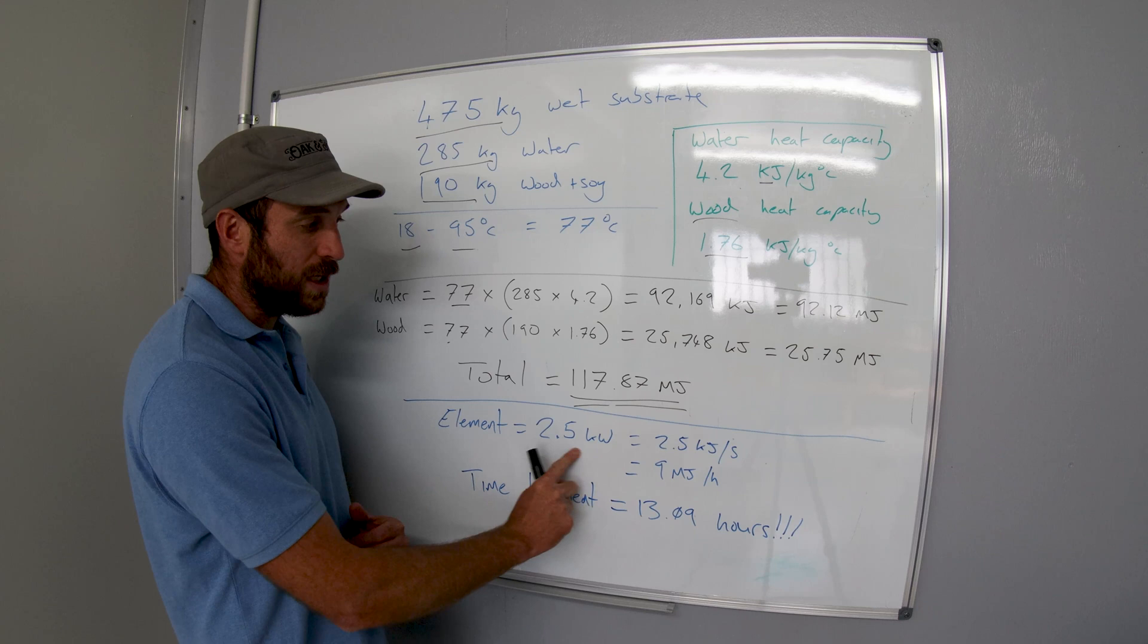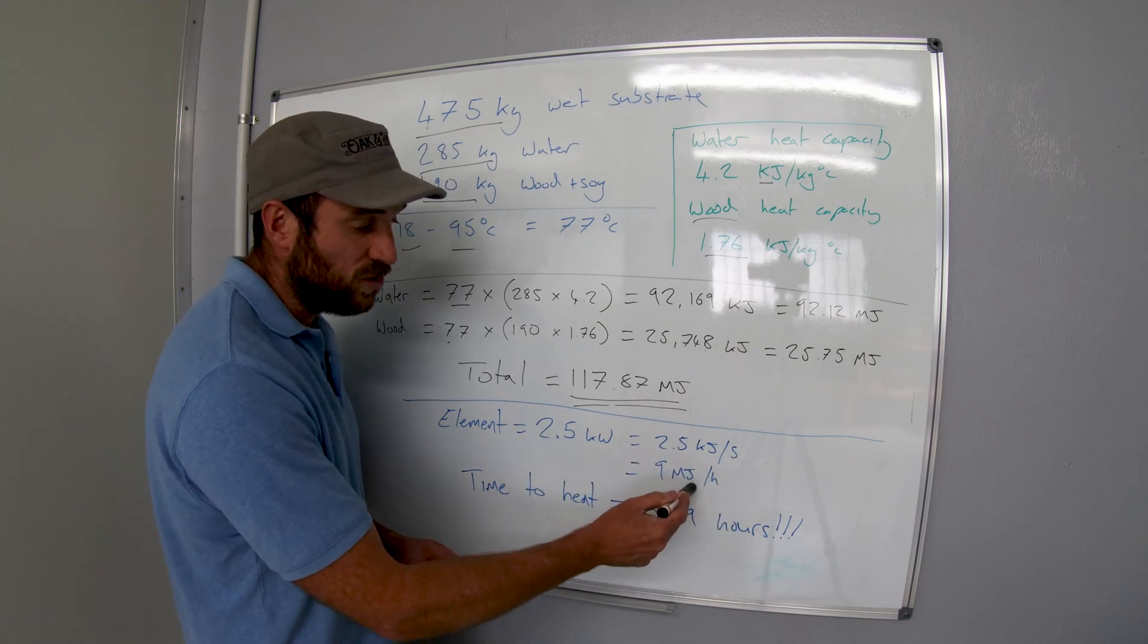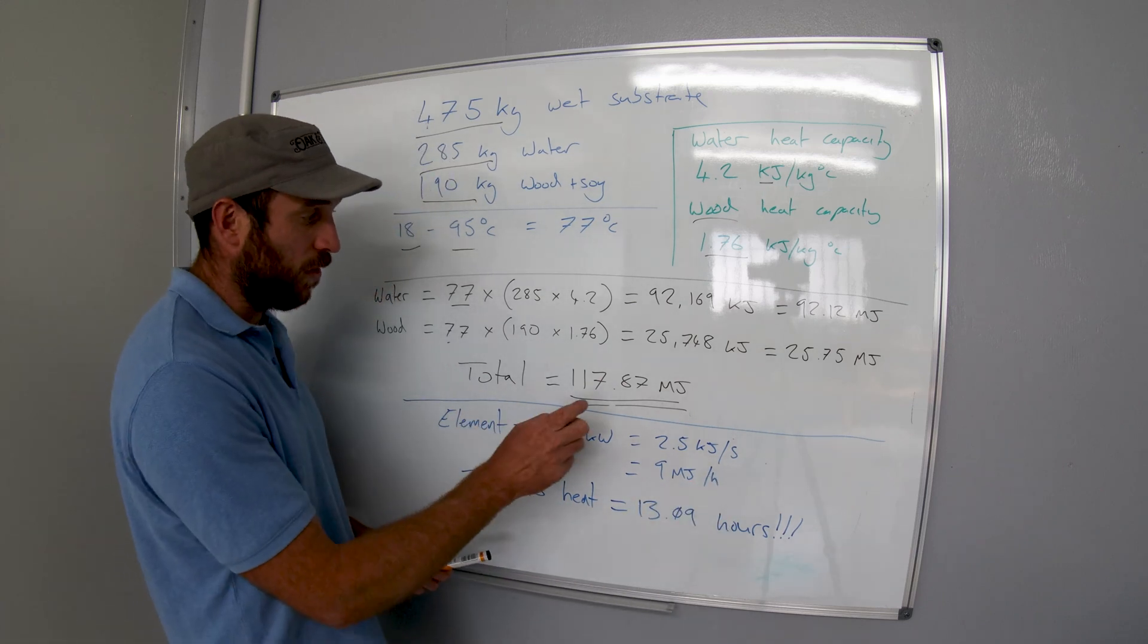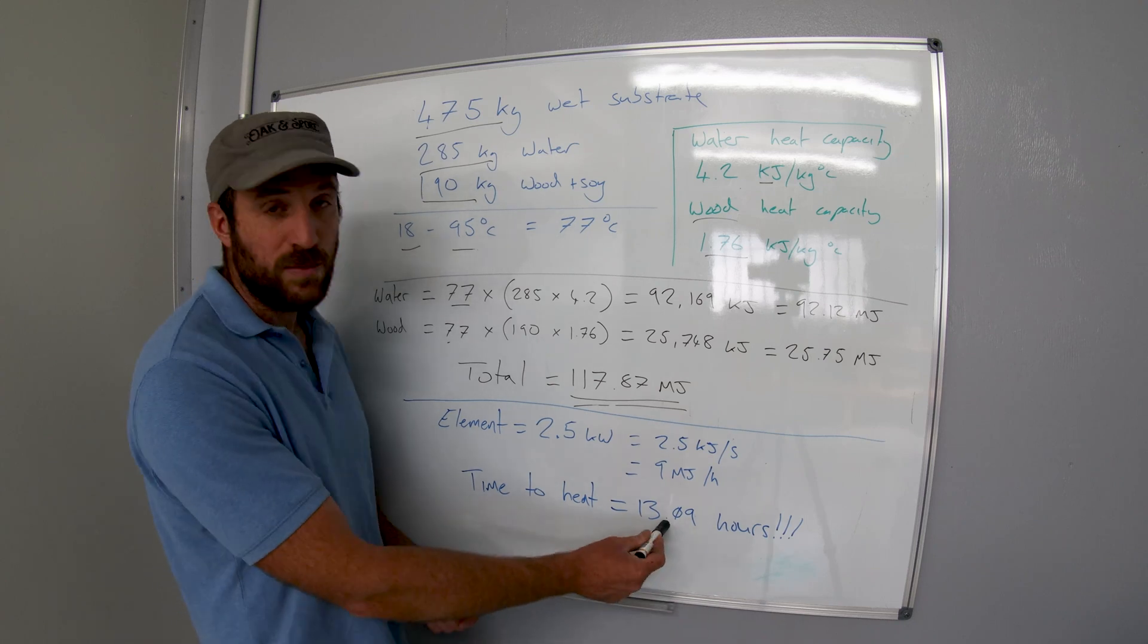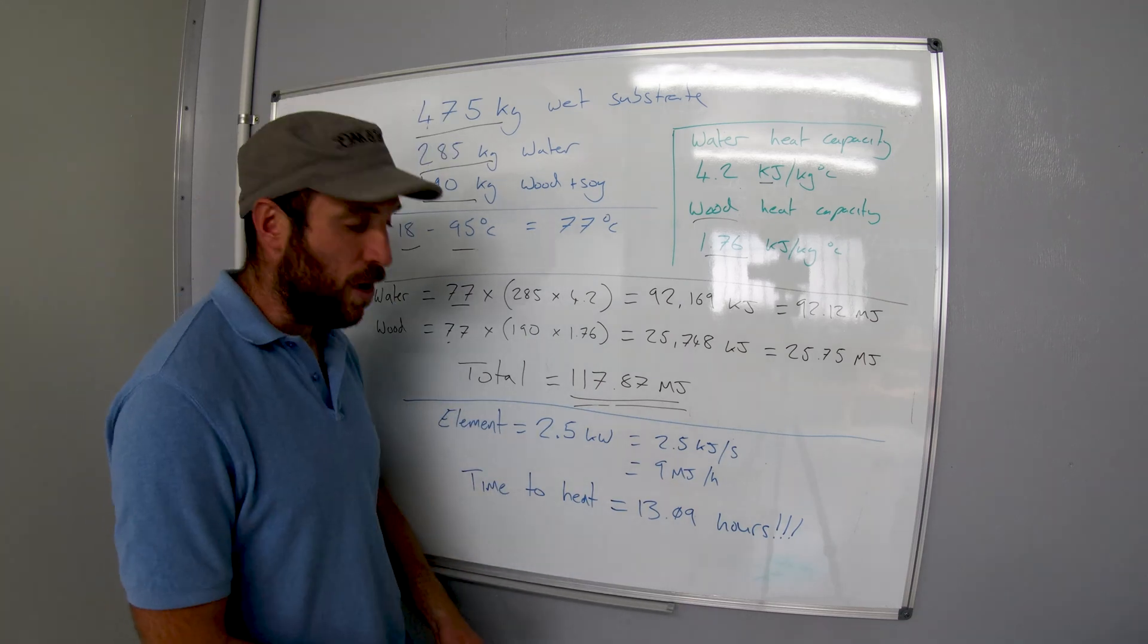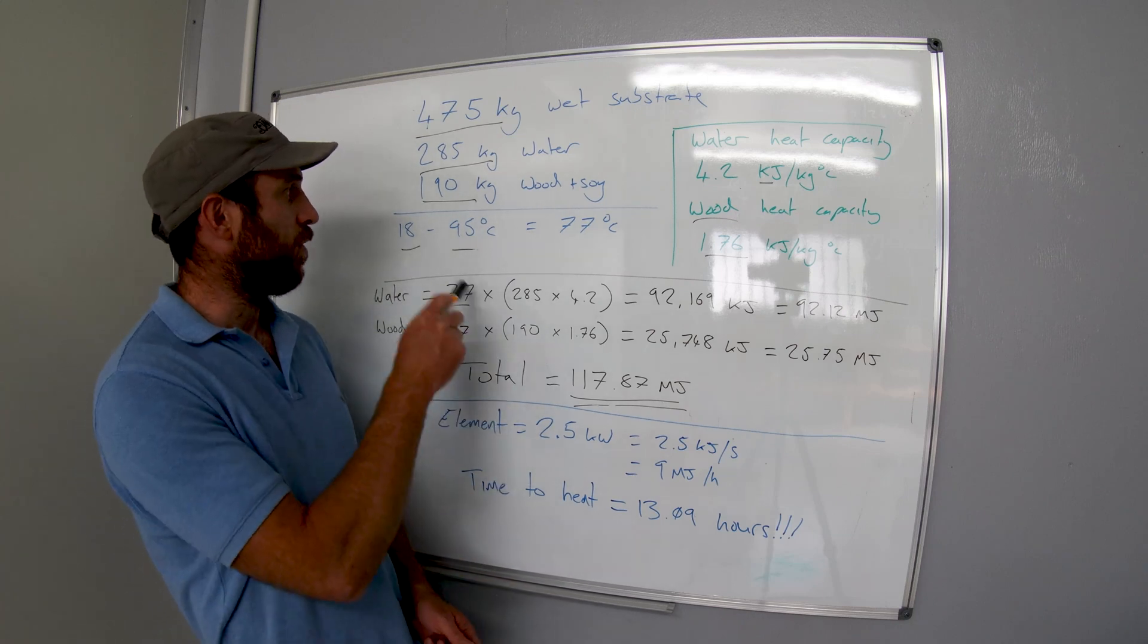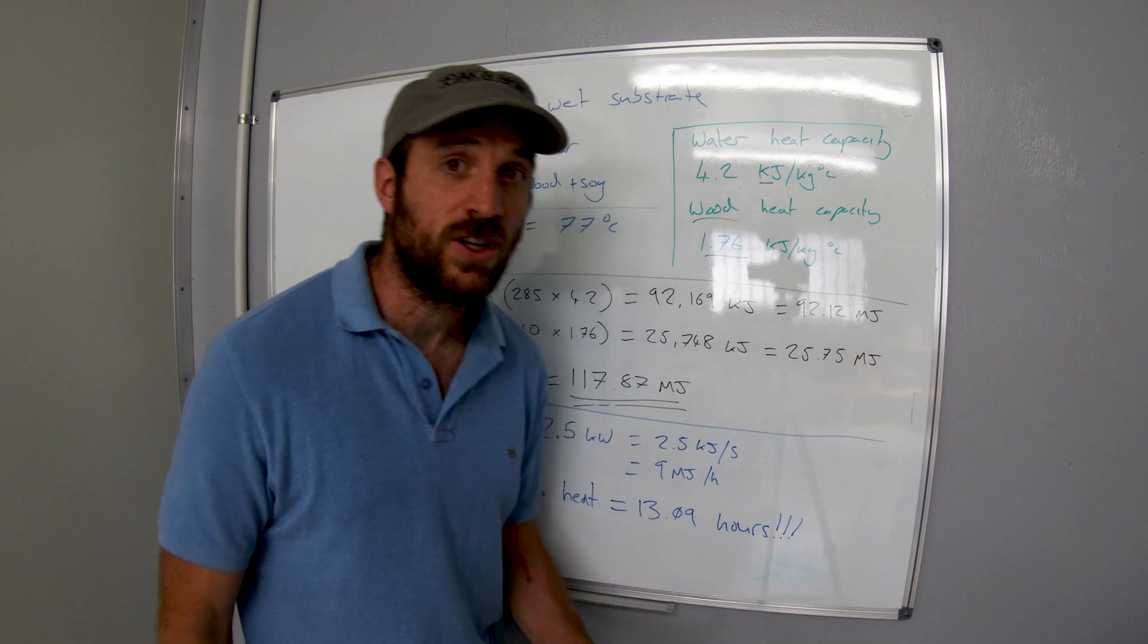Now my element is a 2.5 kilowatt element which gives me 2.5 kilojoules per second which equals 9 megajoules per hour, and we can simply then divide this by 9 megajoules per hour and it gives us 13.09 hours. So it's going to take my 2.5 kilowatt element 13 hours to heat my substrate up from 18 to 95 degrees.